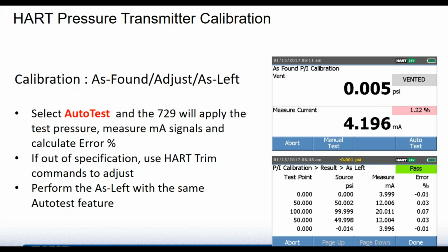Again, if it's out of adjustment, you need to do your HART trim and then repeat your as left to get those results. And again, it has that same auto test feature, so you don't have to do any hand pumping. Really increases how quick that process is done and decreases the time spent. So again, when you finish your calibration, all this information is also documented.